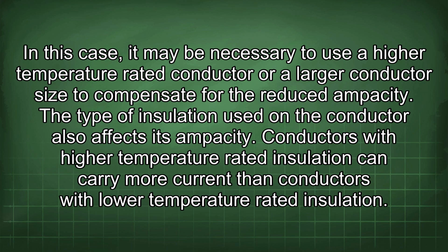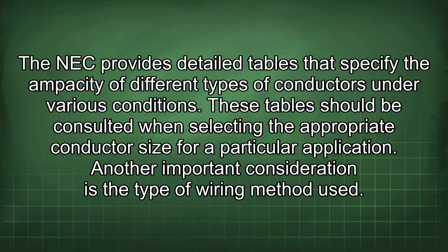The type of insulation used on the conductor also affects its ampacity. Conductors with high temperature rated insulation can carry more current than conductors with lower temperature rated insulation. The NEC provides detailed tables that specify the ampacity of different types of conductors under various conditions. These tables should be consulted when selecting the appropriate conductor size for a particular application.